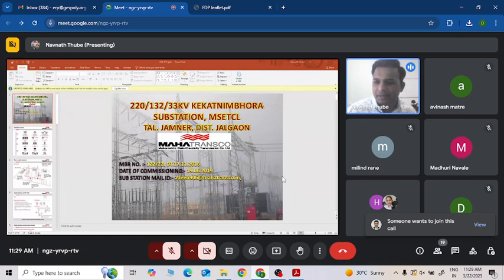Now in a digital substation, what happens? All this cable work from the switchyard MB to the control room is replaced by a single optical fiber cable. For the substation EHV equipment, there is one processing unit which converts our analog data into digital, and through fiber optic the same data can reach our control room through a single cable instead of a lot of bunched cables, and all this avoids the total copper cabling work.